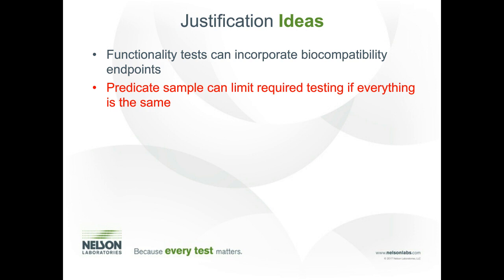As long as your device is locked down enough from a material and process standpoint, we could implement a lot of these biological endpoints, risk assessments, into these functionality tests so we're not doing unnecessary animal tests. Remember the three R's for animal tests. We're really looking at ways we can reduce the need for these animal tests, and really try to get the safety evaluation done without doing unnecessary animal tests.